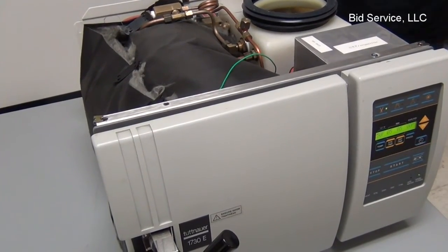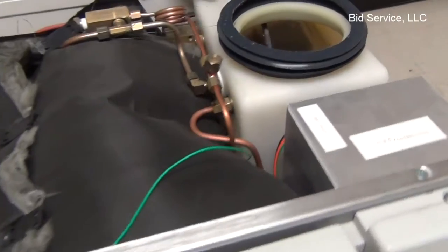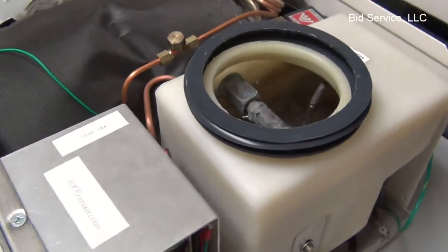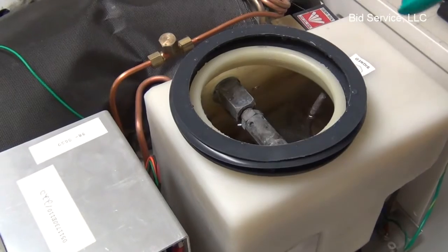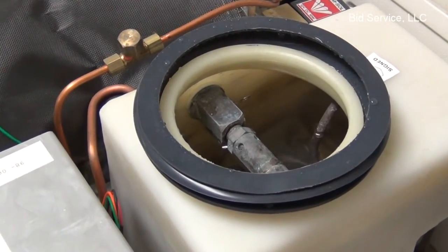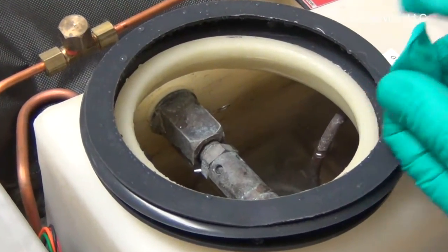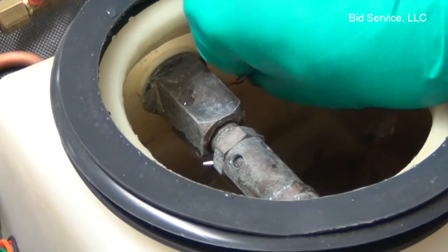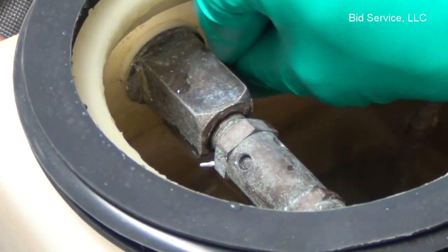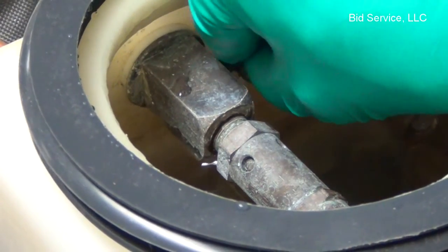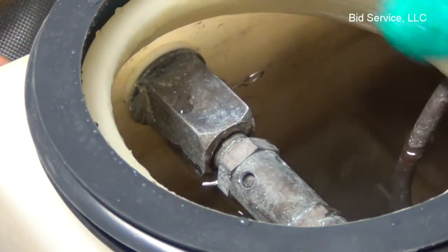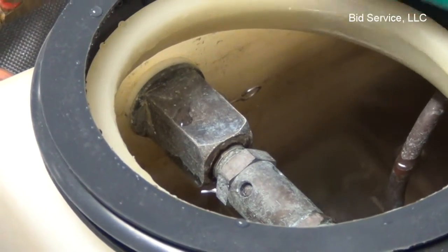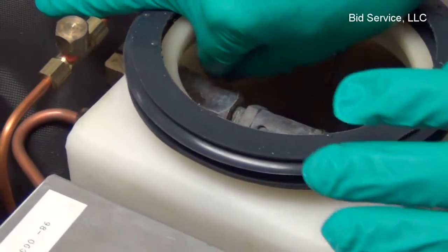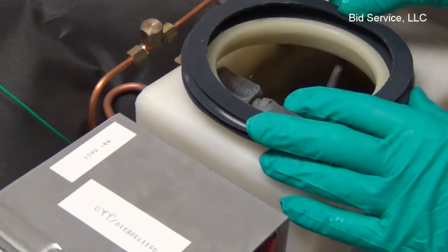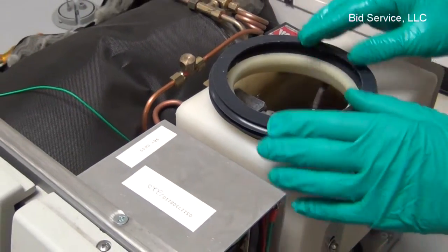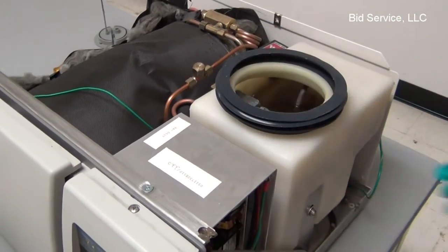And periodically, if you take a look through here, you'll see that there's a little pin that sticks out. What that actually is, is a permanently mounted pin that cleans the little tiny jet valve in there. So you simply go in and move it back and forth in this fashion here. If you get a low heat error, that will occur. But also in the manual there is a whole section on preventative maintenance and some suggestions as to when you should periodically set up a schedule for this.